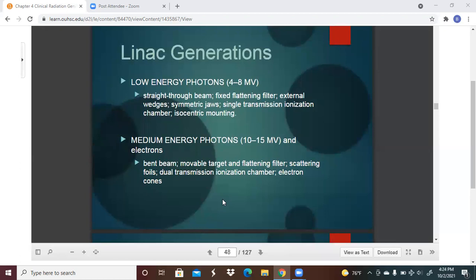So low energy photons, anywhere from 4 to 8 MV, straight through beam, a fixed flattening filter, or in some cases flattening filter free, depending on what is commissioned at your site. External wedges, which I don't know exactly how common that is anymore. There's a lot of EDWs out there. Basically the wedges, by taking the jaw and moving it across, the enhanced dynamic wedge, where the jaw moves across the field at a certain rate. But some places may still use those hard wedges that are external. There are advantages to that in planning. You've got symmetric jaws sometimes, single transmission ionization chamber, isocentric mounting.